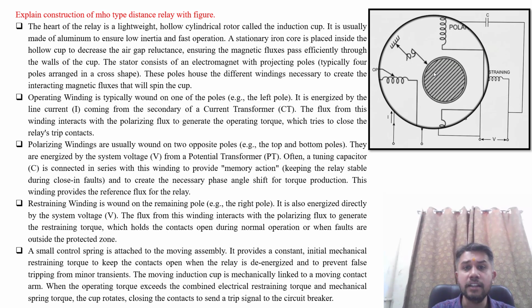A stationary iron core is placed inside the hollow cup to decrease the air gap reluctance, ensuring the magnetic fluxes pass efficiently through the walls of the cup. The stator consists of an electromagnet with projecting poles, typically 4 poles arranged in a cross shape. This is not shown here. These poles house the different windings necessary to create the magnetic flux that will spin the cup.